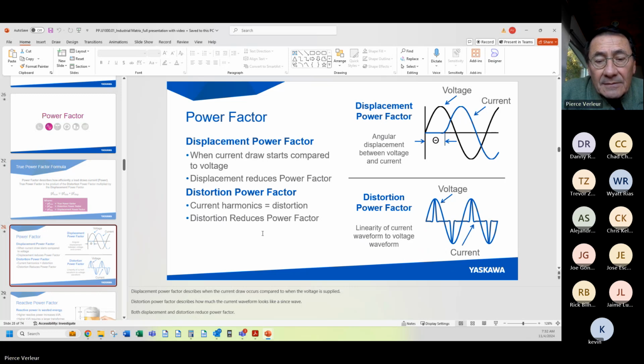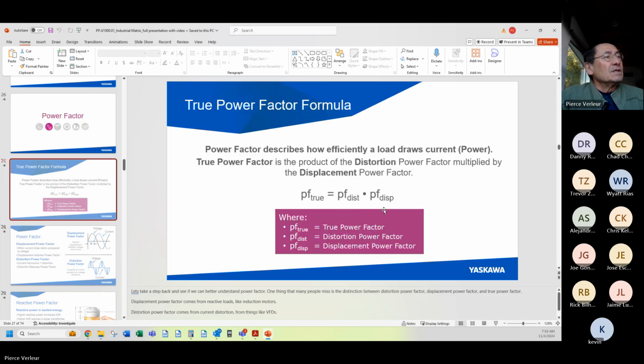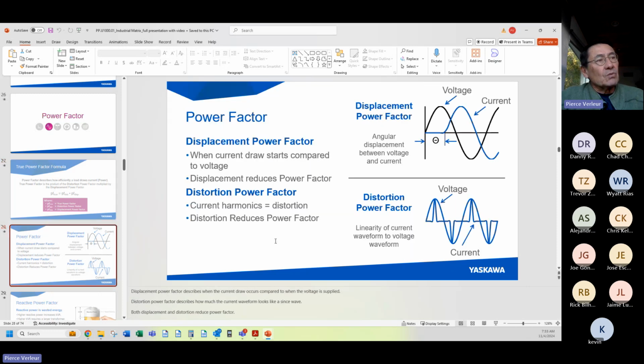It's lost. That's why a lot of your new cars basically turn the engine off after 2 seconds and then start up again when you push on the accelerator. That's an analogy to this lagging current. When the motor unloads, the current lags the voltage, and it causes an inefficiency in the power line. So power factor is displacement power factor, and then this distortion power factor, and the two equal total or true power factor. Distortion power factor is what we deal with today, because a VFD has pretty much no displacement power factor. So we can take that off the table.